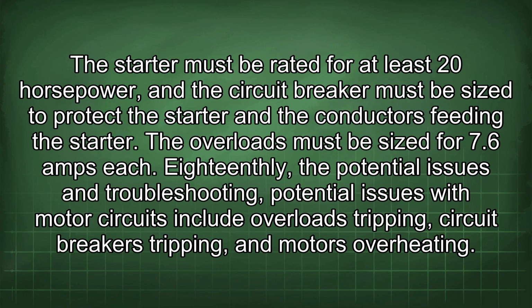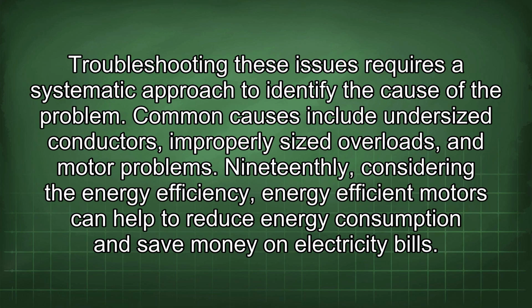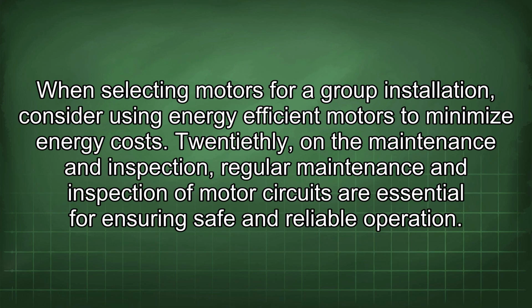18thly, the potential issues and troubleshooting. Potential issues with motor circuits include overloads tripping, circuit breakers tripping, and motors overheating. Troubleshooting these issues requires a systematic approach to identify the cause of the problem. Common causes include undersized conductors, improperly sized overloads, and motor problems. 19thly, considering the energy efficiency. Energy-efficient motors can help to reduce energy consumption and save money on electricity bills. When selecting motors for a group installation, consider using energy-efficient motors to minimize energy costs.